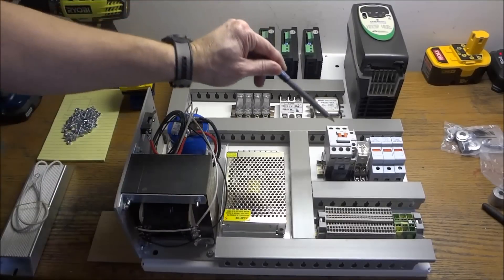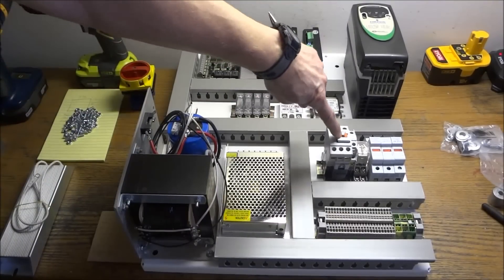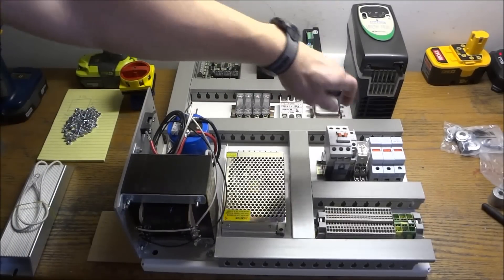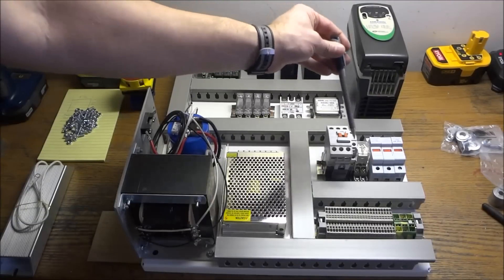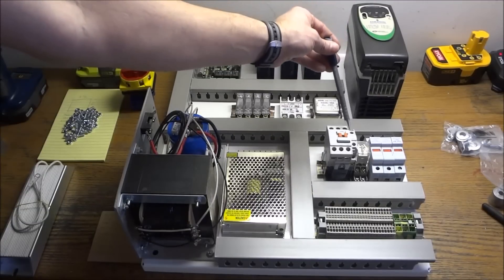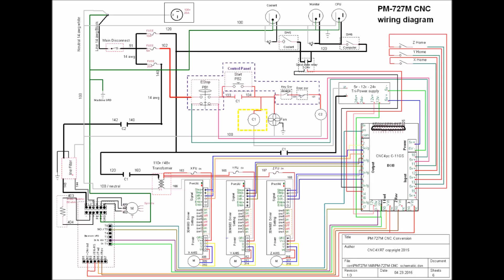Here is our main contactor C1. This is an 18 amp contactor. There are actually three sets of contacts in here with an auxiliary set of contacts. It will energize the coil shown here on our wiring diagram, which will close the contacts. There's three sets of contacts that will close. The dotted line represents the holding circuit. Those sets of contacts, when closed, provide power to the coil until the e-stop is pressed. We have one set of contacts that will energize our 48 volt transformer and another set that will power our tri-power power supply.